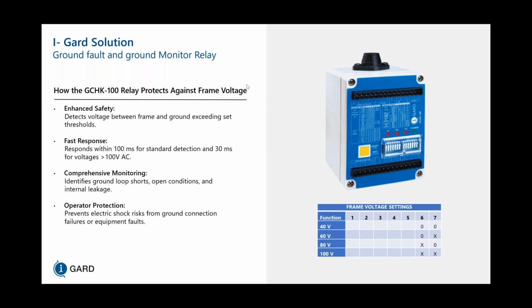Is the purpose of ground check applied to indoor frame and electrical equipment as well, by code or not? Mostly in the mining code, it stipulates that this ground check feature needs to be provided simply because your mobile equipment can be a few kilometers away from the main substation feeding it, and as a result, there's a need to monitor and ensure that the grounds are still intact at the mobile equipment to protect the workers from this frame potential that can occur.